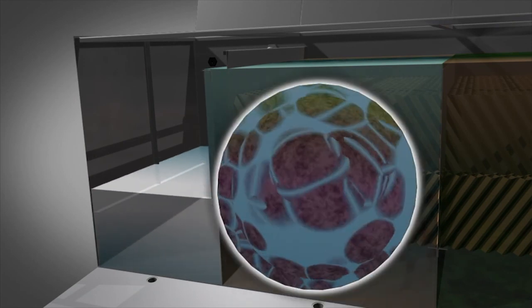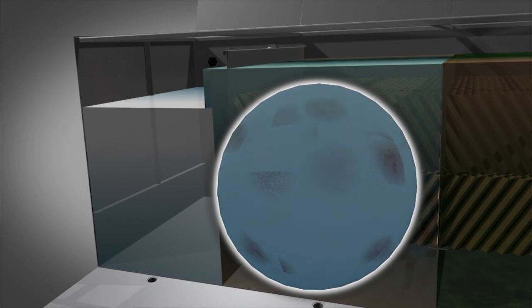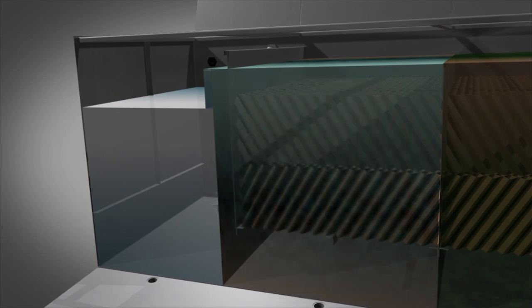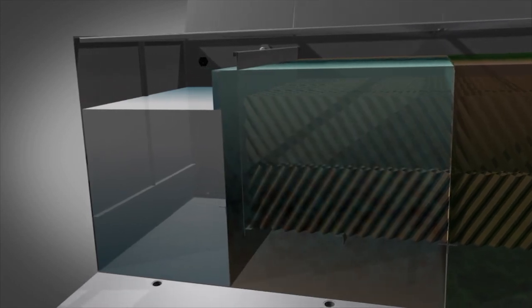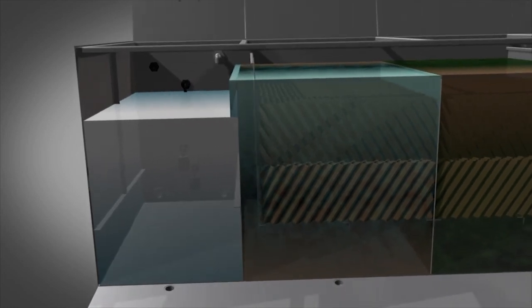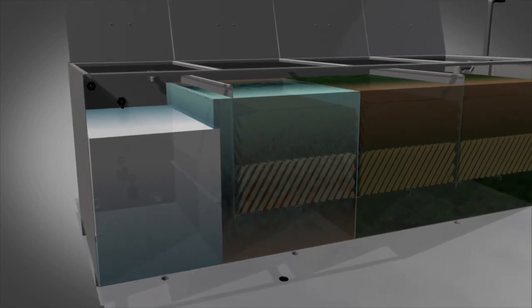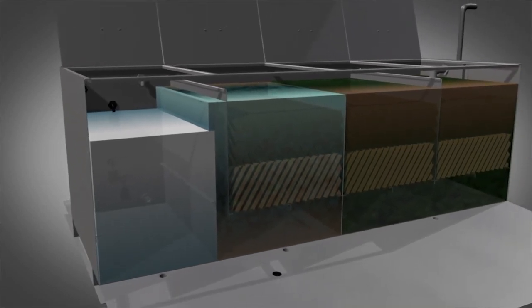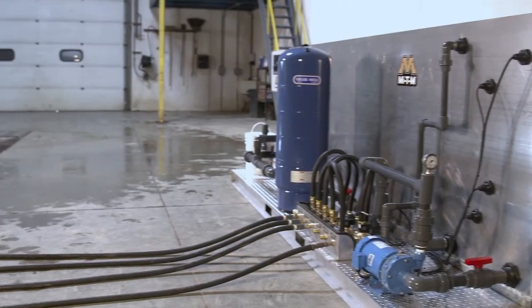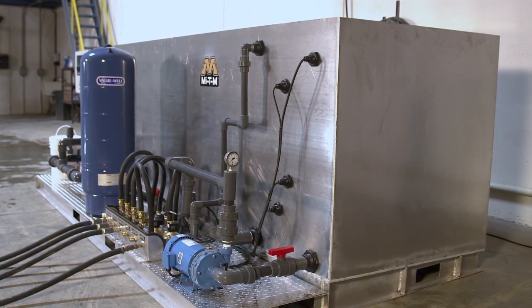The microbes treat the water by consuming any organic materials, including oil, grease, and other naturally occurring substances. The microbes live for this consumption, and the MTM system provides the three basic elements they need to survive: food, environment, and oxygen. Once the microbes have done their work, a pressurized tank delivers the biologically treated water for reuse.